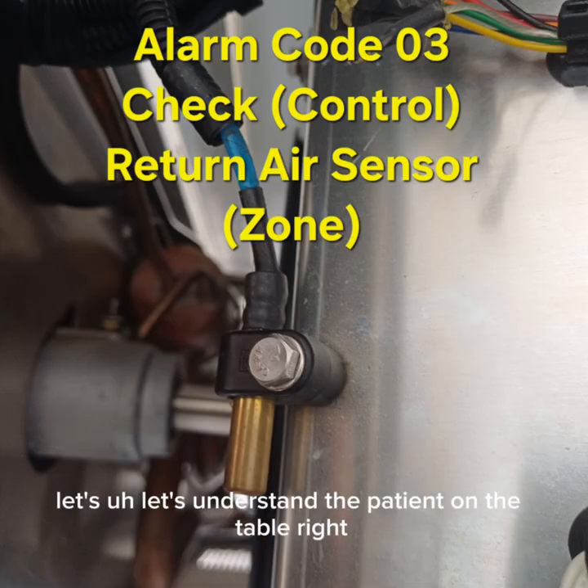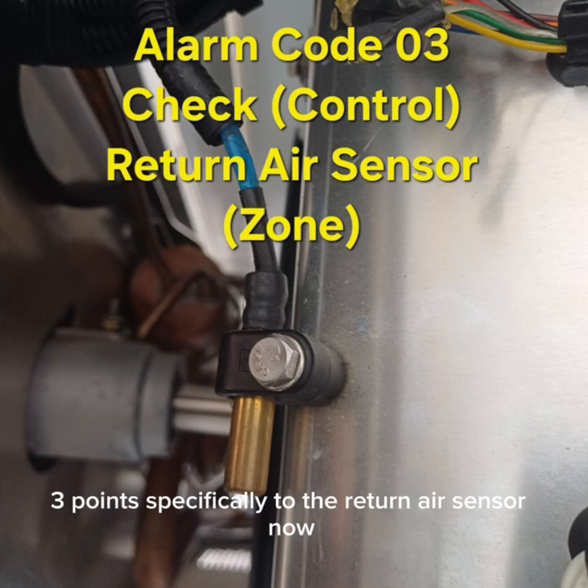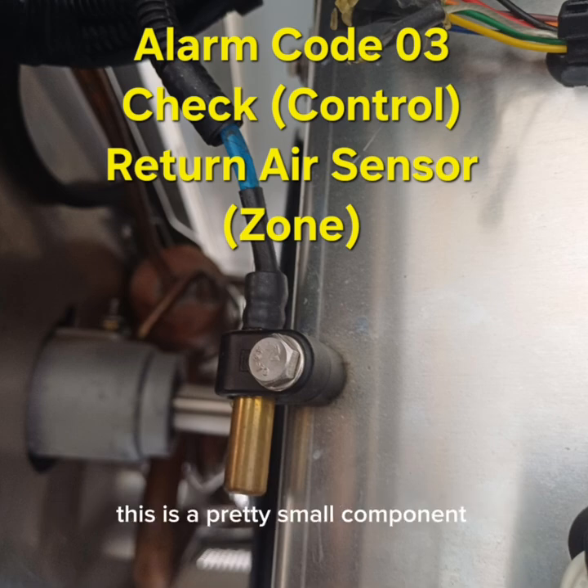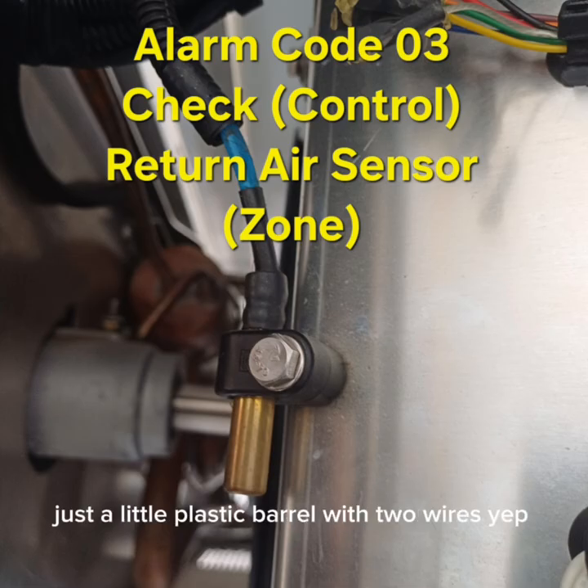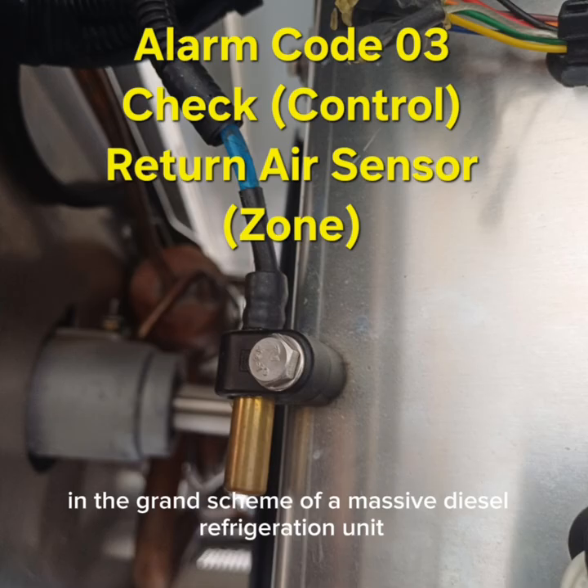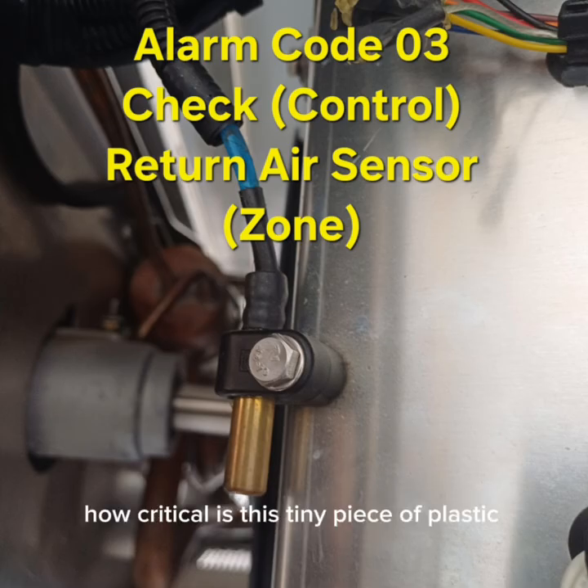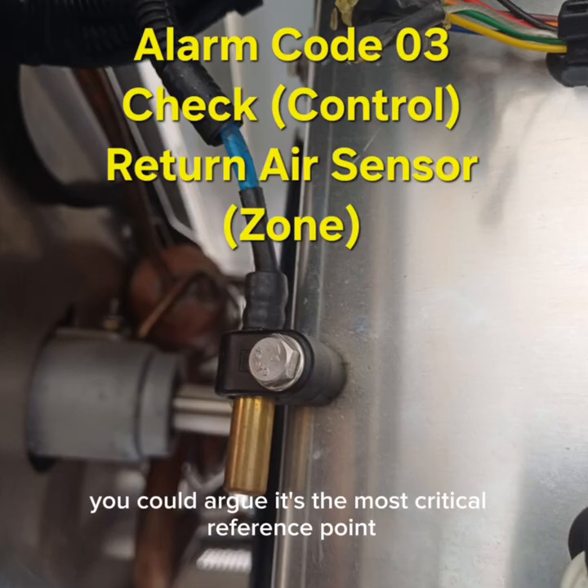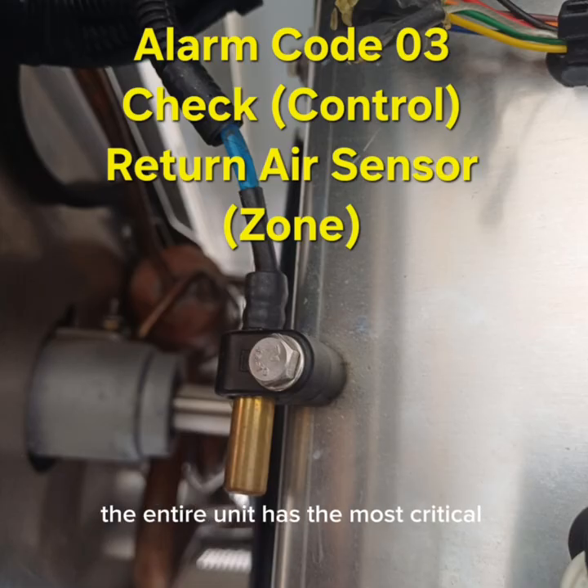First, let's understand the patient on the table. Right, the anatomy. So alarm 03 points specifically to the return air sensor. Now, based on the schematics I'm looking at here, this is a pretty small component, just a little plastic barrel with 2 wires. Yep. In the grand scheme of a massive diesel refrigeration unit, how critical is this tiny piece of plastic? You could argue it's the most critical reference point the entire unit has. The most critical? Oh, absolutely.